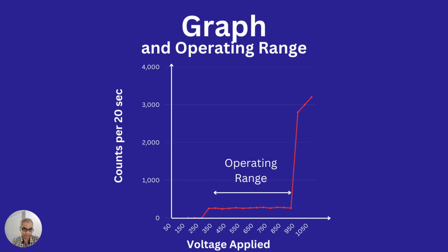If we increase the voltage between the cathode and anode, it is possible that electrons will be pushed, or they will be attracted towards the anode so quickly that they can create some discharge, and because of the discharge the count will be so high that this will be a fake count, because any radioactive particle is not creating one electron, but it is creating more than one electron, and therefore whatever the count you are getting is not the correct count.